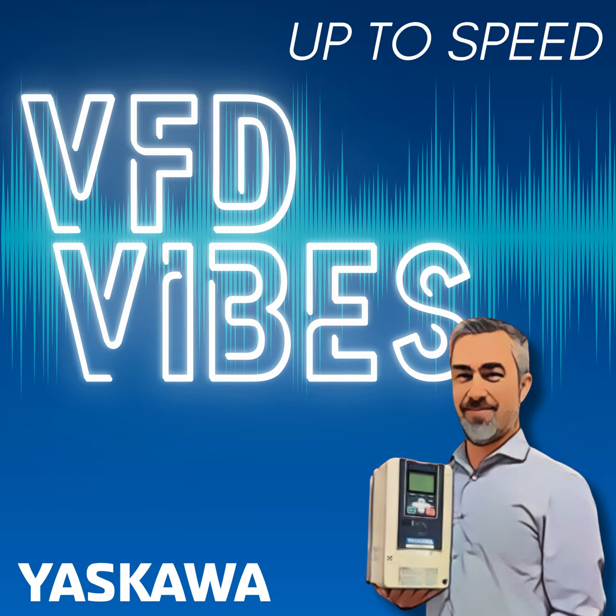When it comes to energy monitoring, whether for energy savings or just trying to see what's going on, the drive can act as kind of a different sensor. You brought up a good one with the DC bus voltage. Some people may say, hey, my voltage coming in is 480, I know it's 480, that's what it's supposed to be. But if you were to monitor the DC bus voltage, you may see it spike up all of a sudden, and that would help indicate something is going on with your main lines.